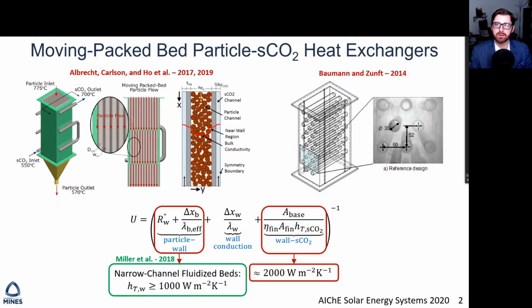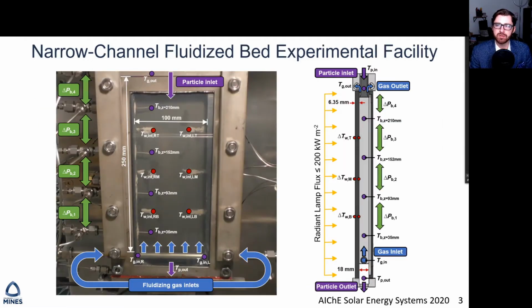Prior work at Mines has demonstrated that significantly higher particle wall heat transfer coefficients in excess of 1,000 watts per meter squared Kelvin can be achieved in small narrow-channel fluidized beds, suggesting that this approach could enable smaller, more cost-effective heat exchangers for particle-based thermal energy storage. Towards that goal, we established the new larger-scale narrow-channel fluidized bed experimental facility. The bed is 18 millimeters deep, multiple times larger than those required for moving packed beds.